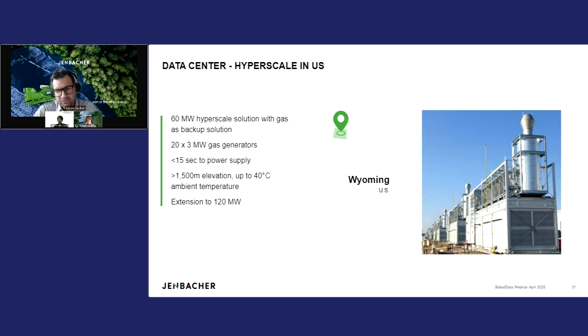Then we have one of our first installations, roughly 7 years back. That's how we started, introducing our units to a hyperscale installation in the US, in Wyoming. It's a 60 megawatt installation where no diesel generators have been placed on site. The main reason we were chosen is because we have the same start time and performance as a diesel generator, but with a lean burn gas engine at 3 megawatts.